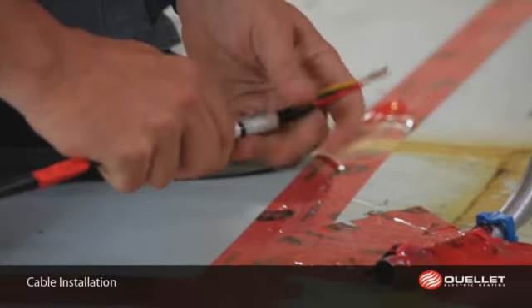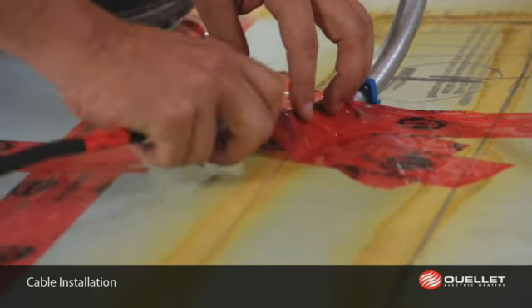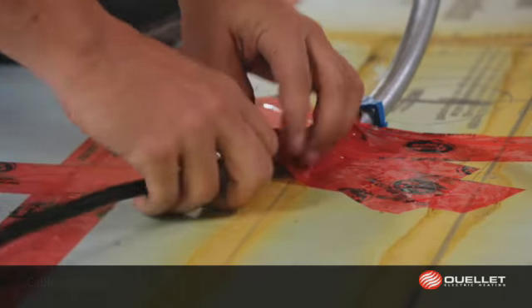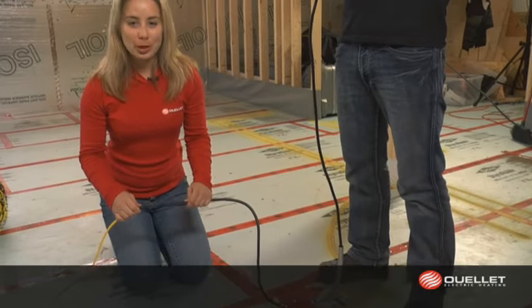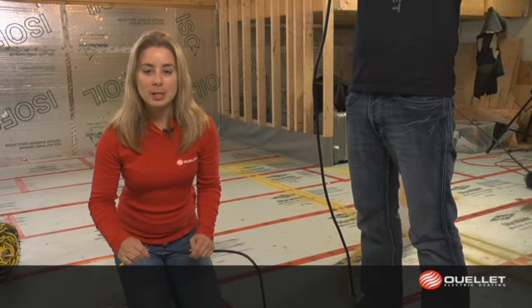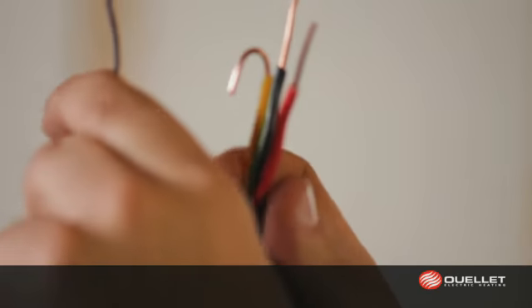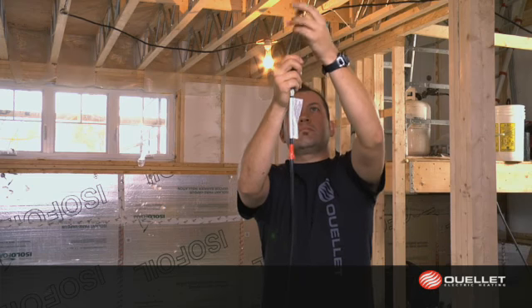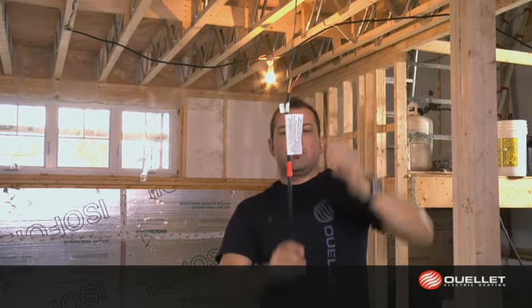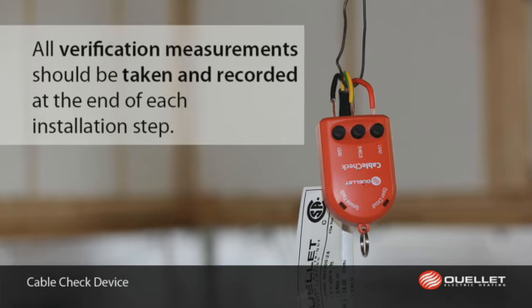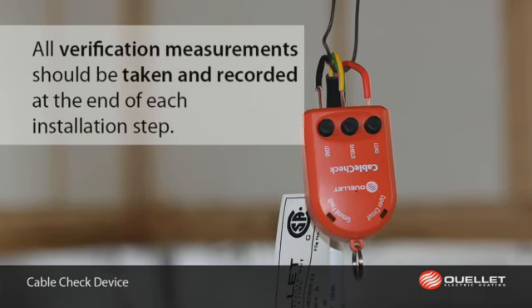Slide the coil lead into a wireway installed underneath the future location of the thermostat. The mechanical joint must remain outside the wireway and must be embedded in the concrete slab. Make sure that the end of the non-heating cable remains dry before and during the installation. Plug in the cable check device that is included in your kit. It will assure you of the integrity of your cable during your installation. However, we ask that all verification measurements be taken and recorded at the end of each installation step.